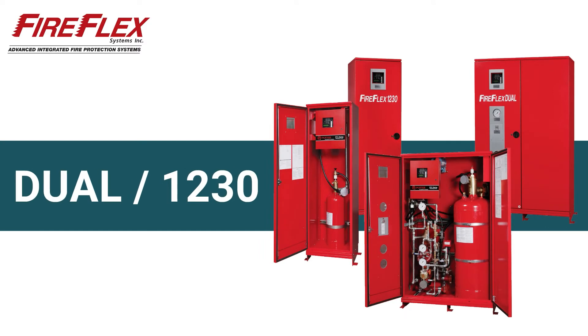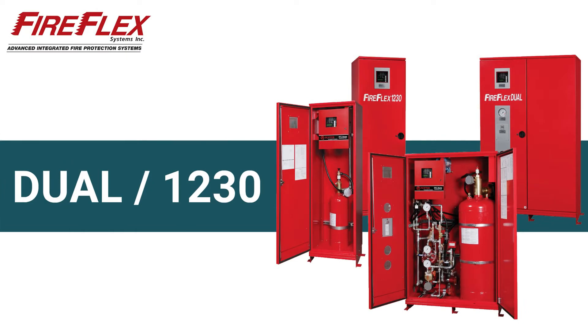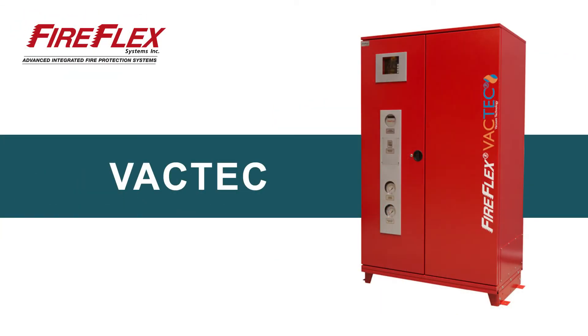The FireFlex Dual and FireFlex 1230. In the case of the FireFlex Dual, it is a pre-action system in combination with a Clean Agent system integrated into the same cabinet and using the same control panel. For the first mechanism of extinguishment, we have the Novec 1230 Clean Agent system, and you have the sprinklers available to protect other parts of the building. The FireFlex VacTec System uses vacuum as a supervisory gas inside the piping network, providing better corrosion resistance as well as interesting hydraulic benefits.